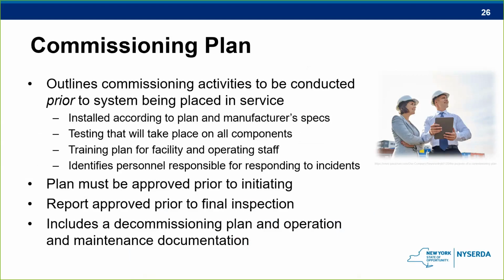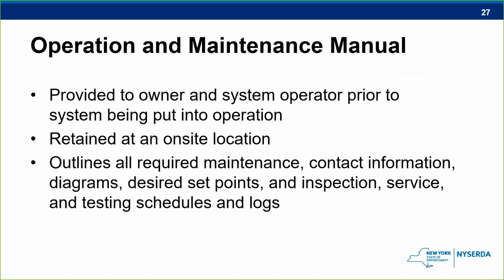So this is no surprise, like many other types of systems, commissioning needs to take place to ensure that energy storage systems will perform as they're intended to. And it's required prior to the system being placed in service. The plan needs to be approved prior to starting commissioning, and the report needs to be approved prior to final inspection. The commissioning plan would include a narrative description of the activities that will be accomplished during each phase of commissioning, including who would be doing what. An operation and maintenance manual must also be provided to both the system owner or their authorized agent and to the system operator before it's put into operation. And the system needs to be operated and maintained in accordance with the manual, and a copy of the manual needs to be retained at an on-site location and include testing schedules and, more importantly, even logs of when testing was done throughout.